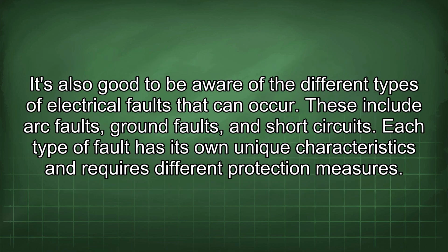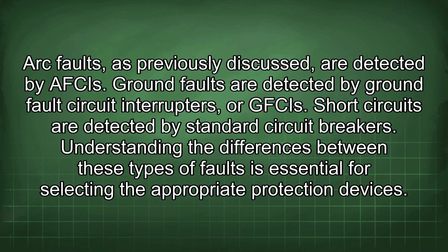It's also good to be aware of the different types of electrical faults that can occur. These include arc faults, ground faults, and short circuits. Each type of fault has its own unique characteristics and requires different protection measures. Arc faults, as previously discussed, are detected by AFCIs. Ground faults are detected by ground fault circuit interrupters, or GFCIs. Short circuits are detected by standard circuit breakers. Understanding the differences between these types of faults is essential for selecting the appropriate protection devices.